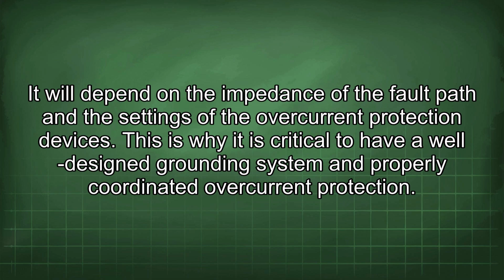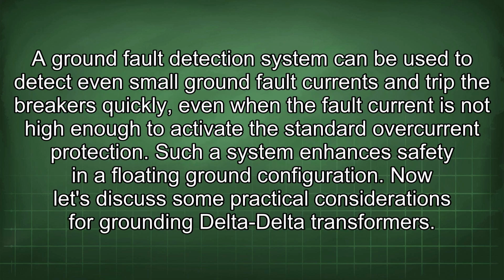This is why it is critical to have a well-designed grounding system and properly coordinated overcurrent protection. A ground fault detection system can be used to detect even small ground fault currents and trip the breakers quickly, even when the fault current is not high enough to activate the standard overcurrent protection. Such a system enhances safety in a floating ground configuration. Now let's discuss some practical considerations for grounding delta-delta transformers.